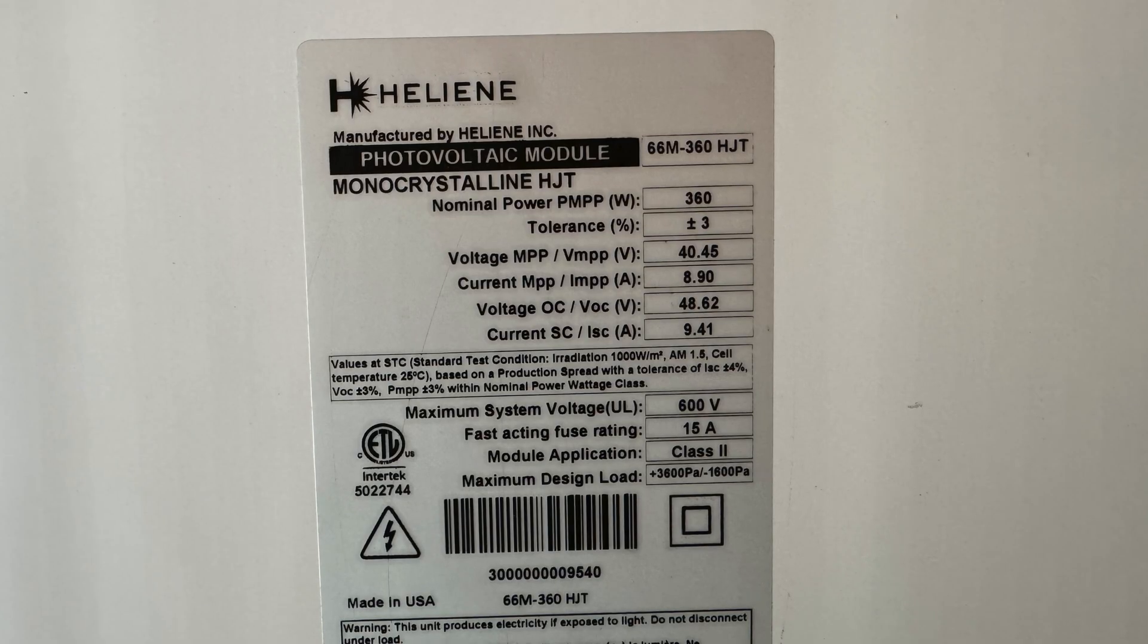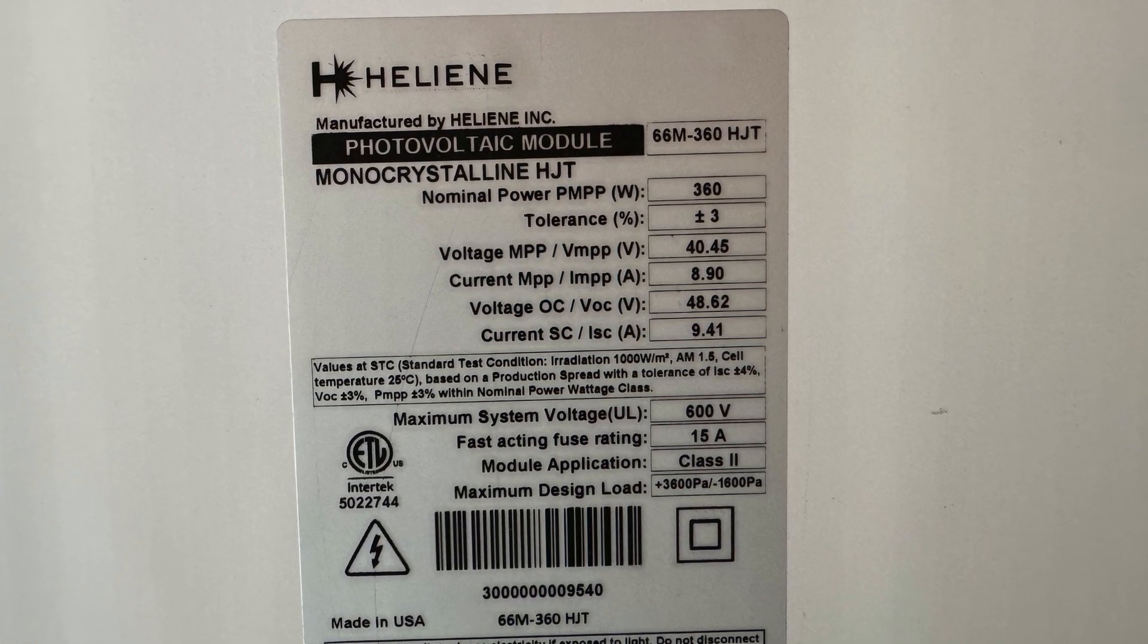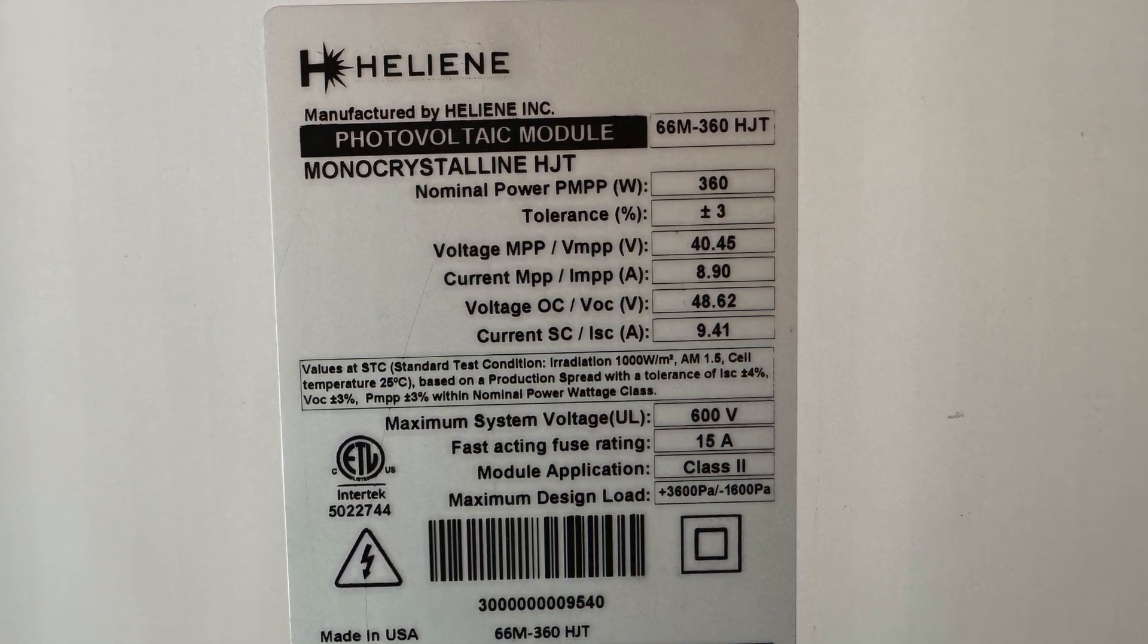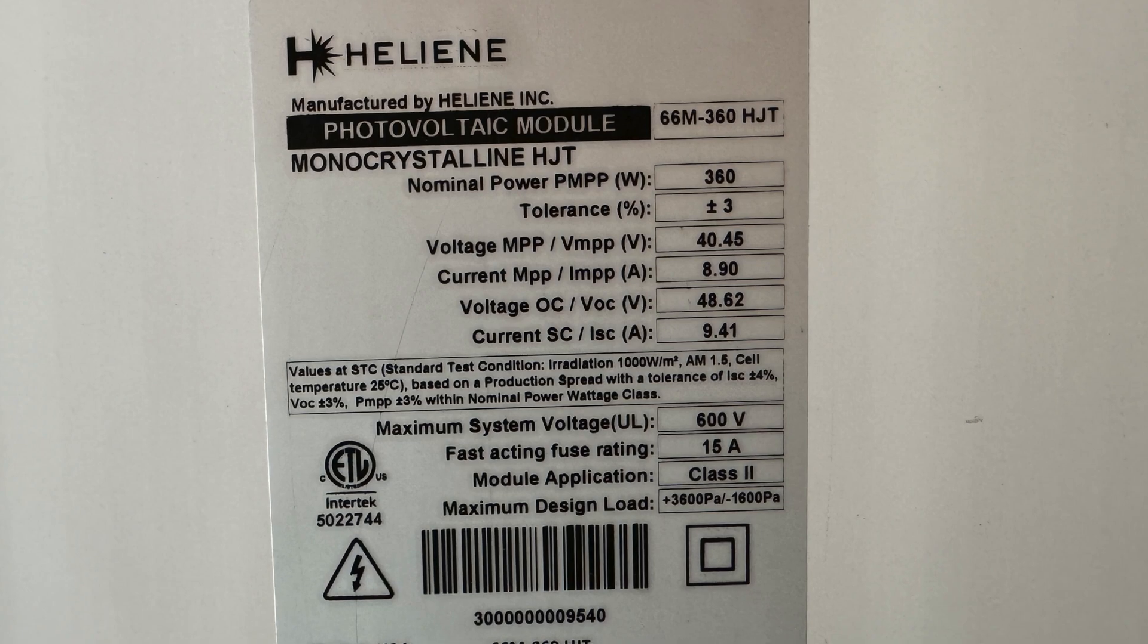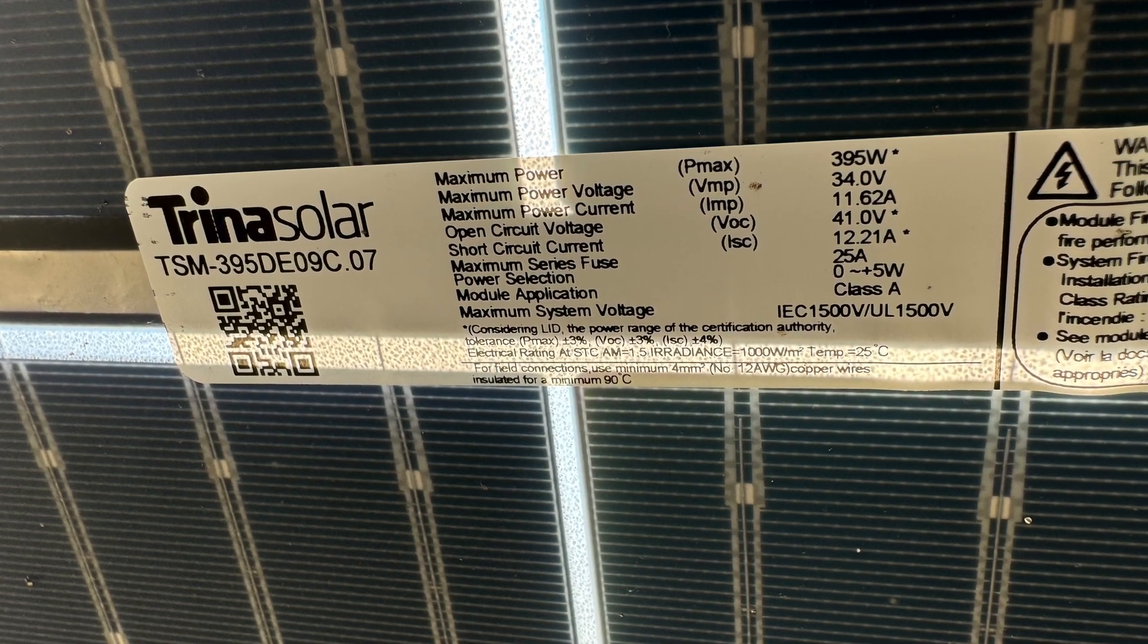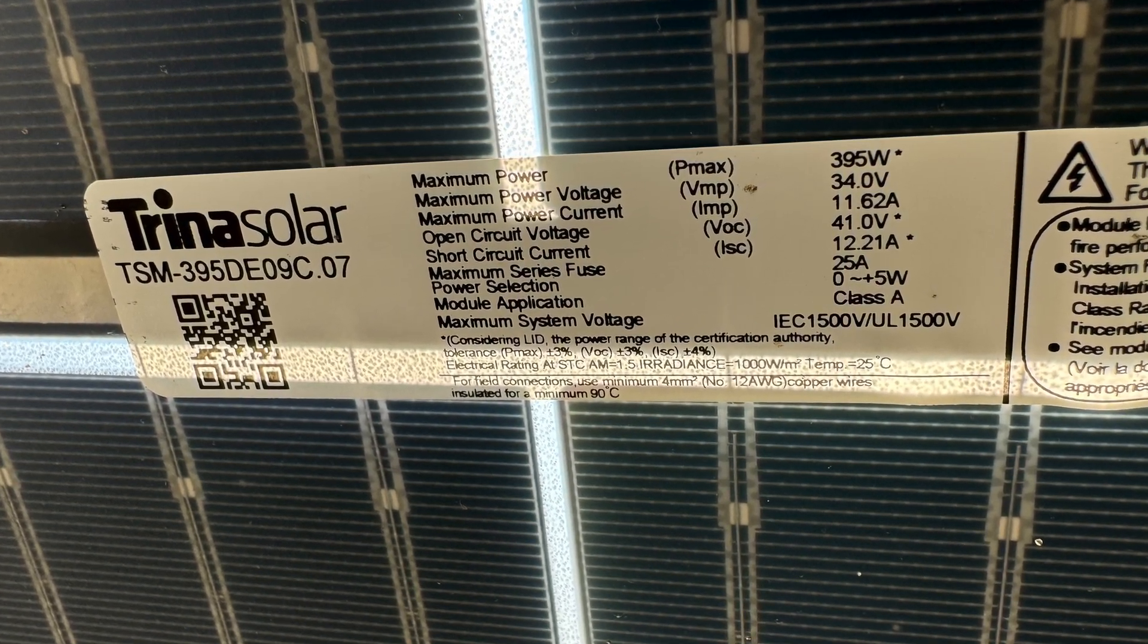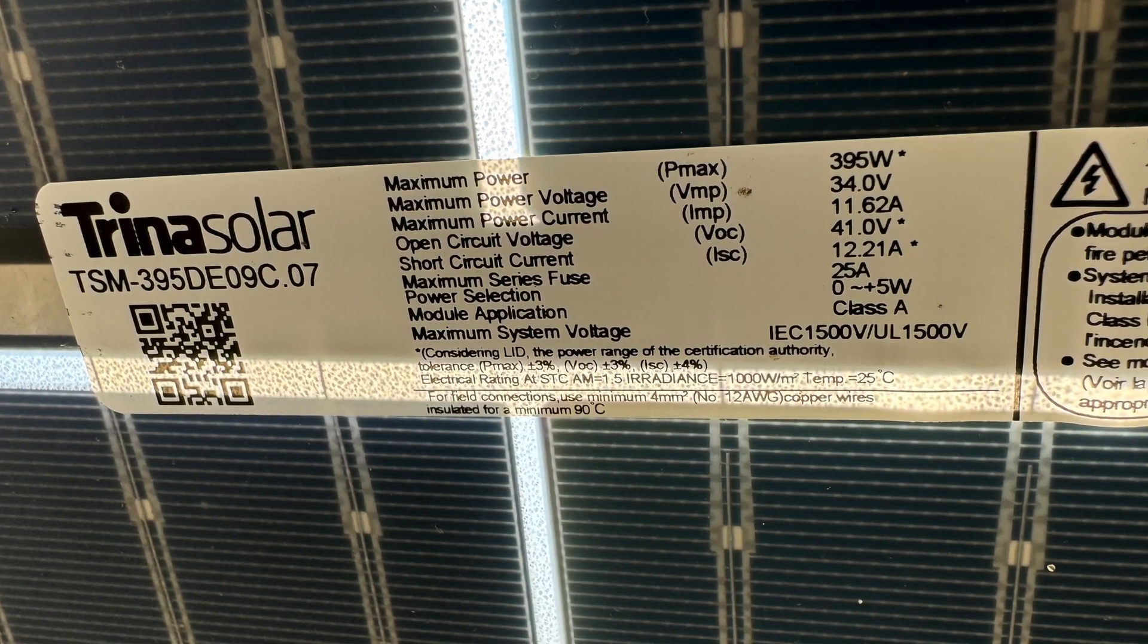Looking at the Heliene 360 watts for the short circuit current I'm looking at 9.41 amps and then for that fuse rating we're looking at 15 amps. For the Trinas we're looking at 12.21 amps for the short circuit current and then a fuse rating of 25 amps.